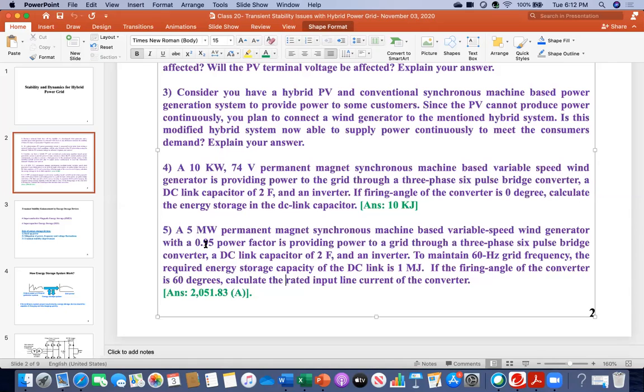And that root 3, if you have used, and voltage value, which voltage value have you used? You have to use the line value 1480.96, that one. Yeah, I use the same one. So then it should not be so low. Yeah, can you check once again? Yeah sure, doctor. And then 5 megawatts, so 5 multiplied by 10 to the power 6 watt. And if you have put 0.95 and you are using a calculator, then you should not get such a deviated result. It's almost half of the result. Yeah.